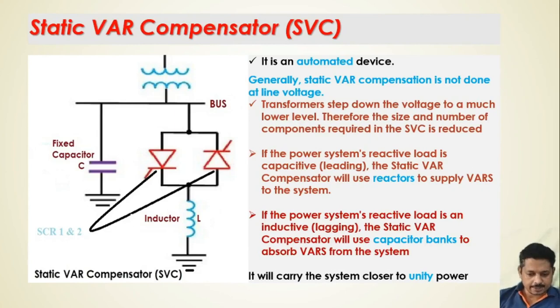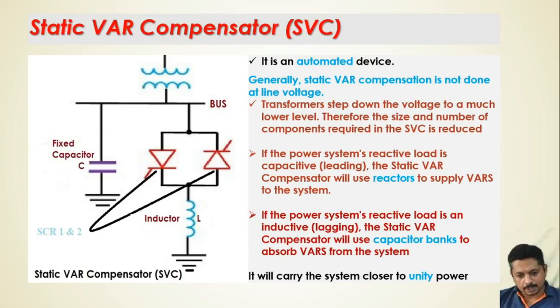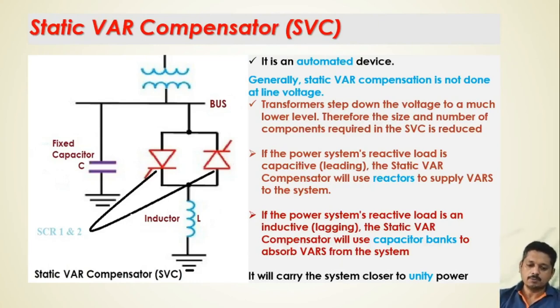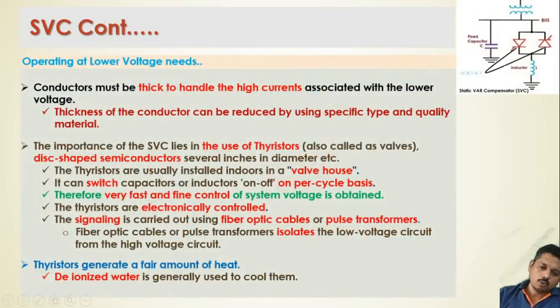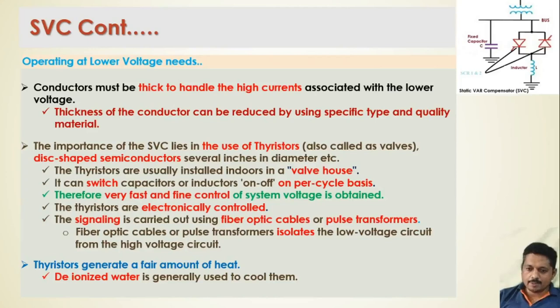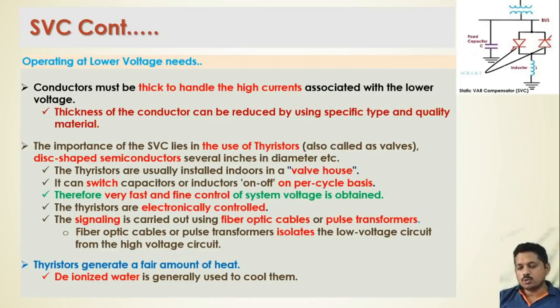This is a simple way to achieve reactive power compensation. If the system is going too leading or too lagging, both are not efficient. We have to keep the system at unity or near-unity power factor. Since the compensator runs on lower voltage, it carries higher current, so we need thick conductors and high-quality material for compensator connections.